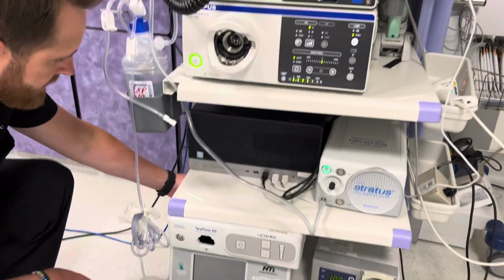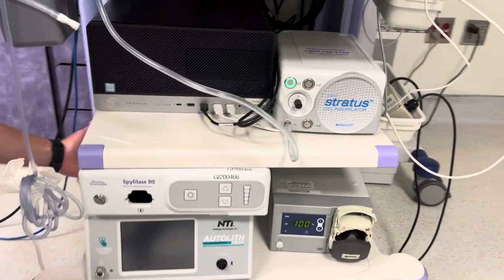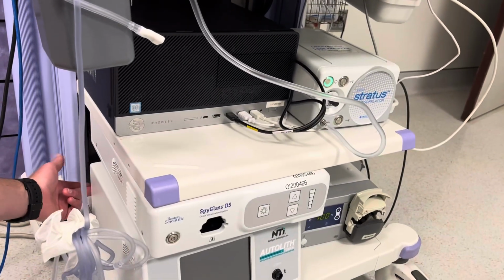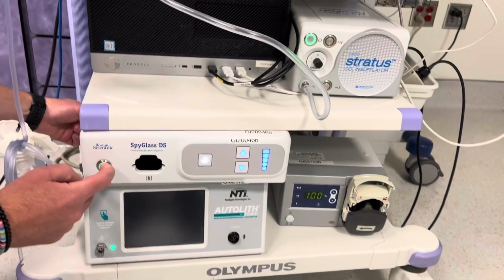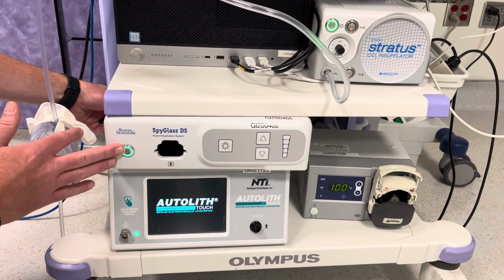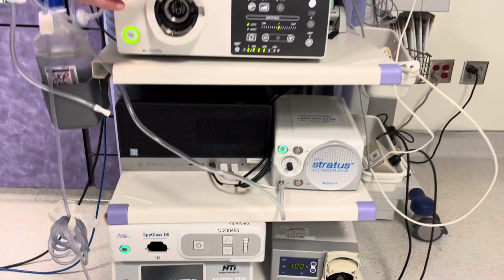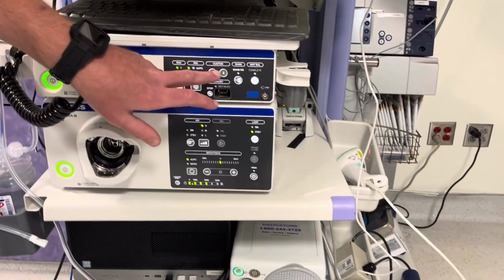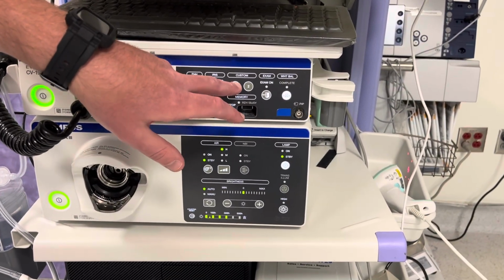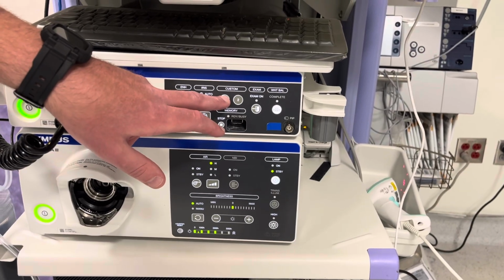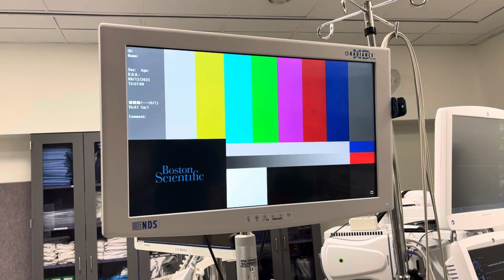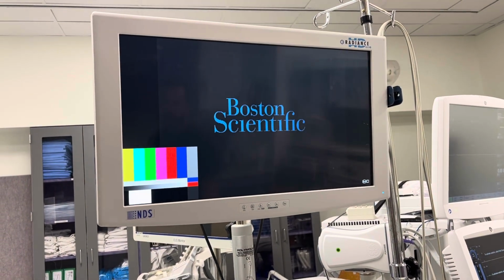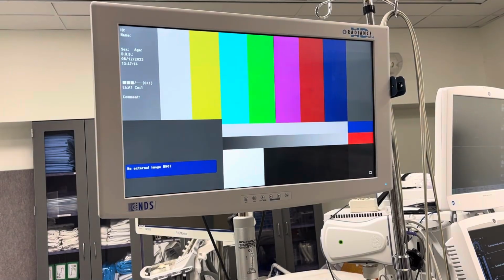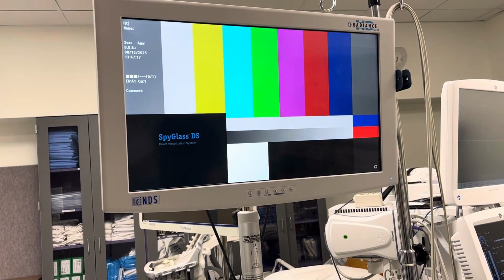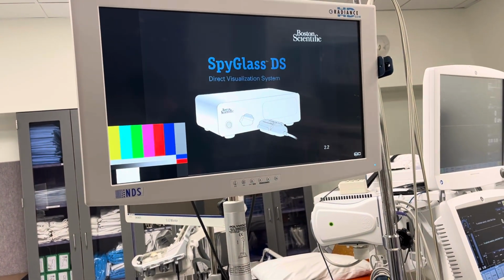Once we have saline connected, we're gonna reach around the back of the EHL console. There's a toggle switch. Turn EHL on, push the power button on Spyglass until you get your green dot here. Once you have your green dot here, you can come up to the Olympus processor and hit the Custom 1 button. Custom 1 will turn on picture-in-picture, and when you look at your monitor, you should see the Boston Scientific logo. As you toggle through Custom 1, it'll change the size and configuration of your image on the screen.